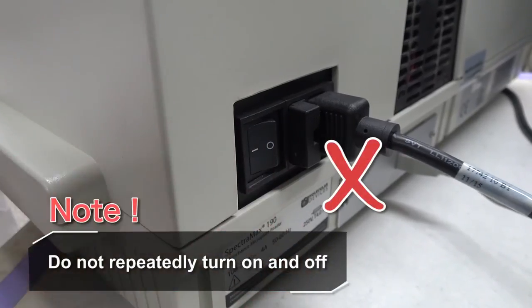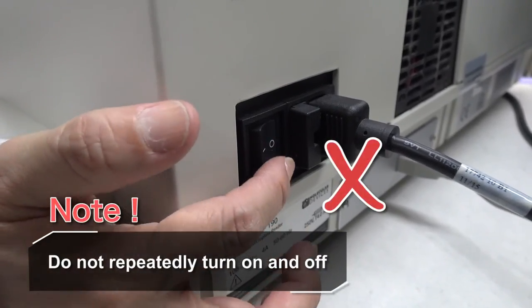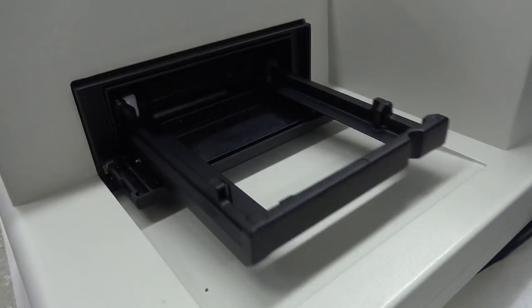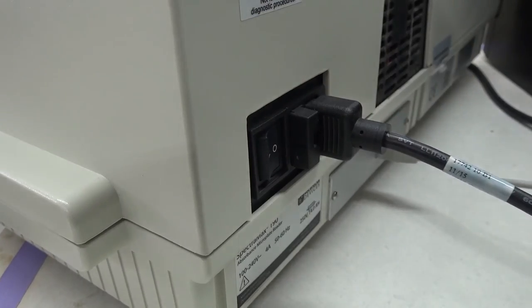9. Repeatedly turning on and off could damage the spectrophotometer. Do not shut down the software and machine until the end of the day or holiday. Put on the dust cover after turning off.